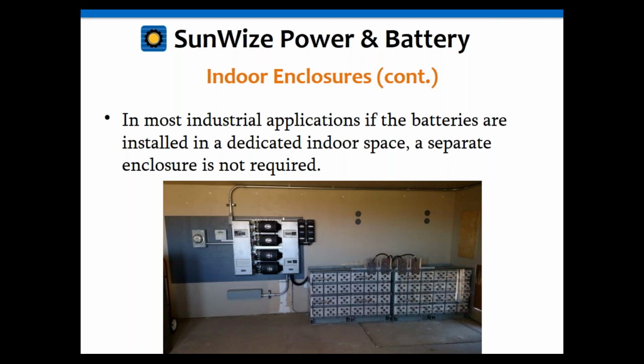In a dedicated room or space like this, a separate enclosure is usually not needed, though it may depend on the local jurisdiction, which may require it anyway. Even though you could walk up and touch some of those components, because it's in a separate room, they may require authorized personnel access instead of a dedicated enclosure. So sometimes no enclosure may be necessary, depending on the application.